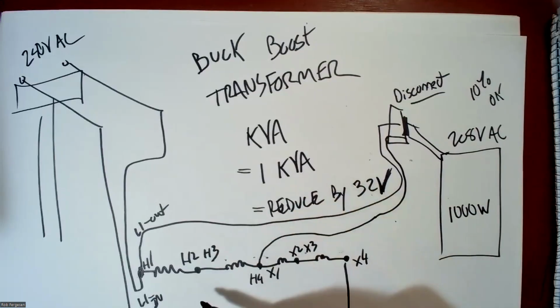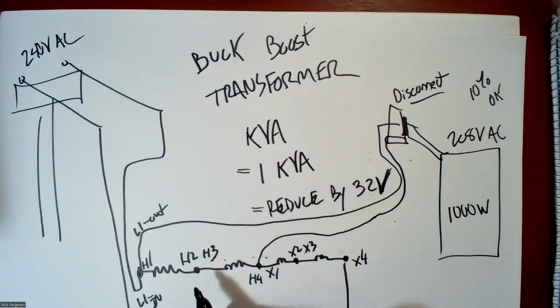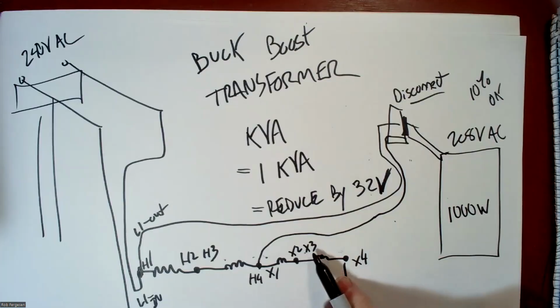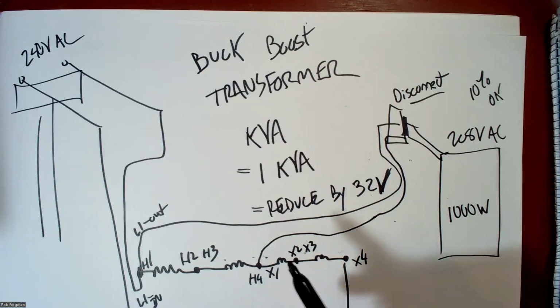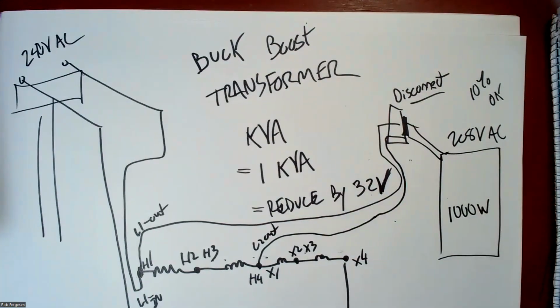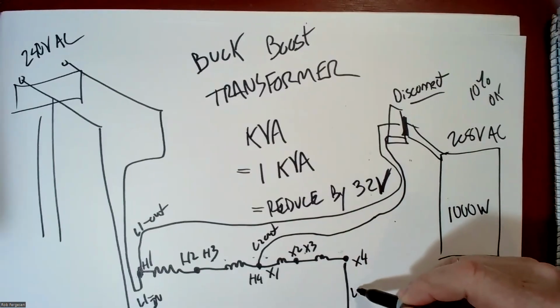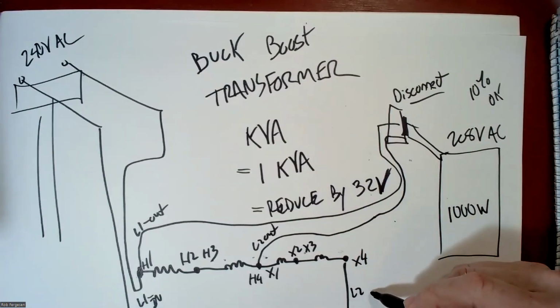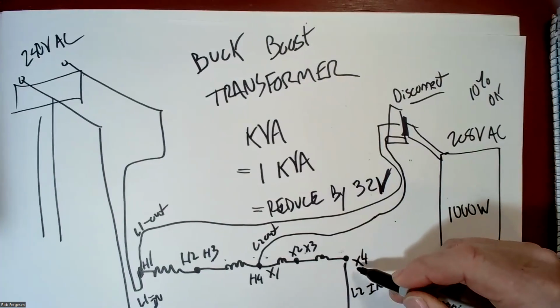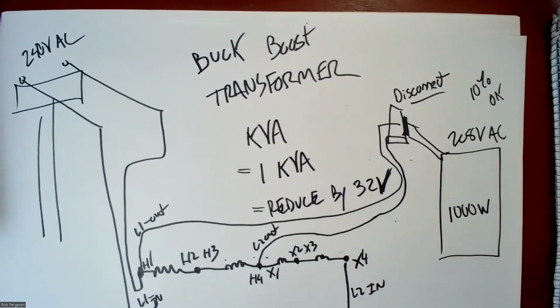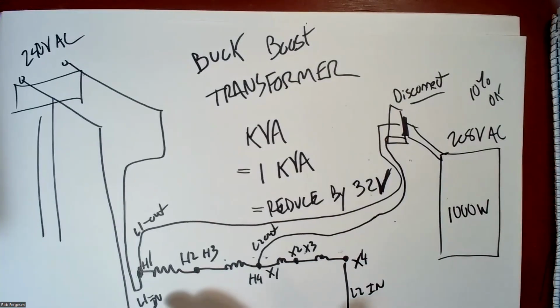When I say jumper, I mean you just wire nut them together. You're going to wire nut those leads together. You're going to wire nut these leads together. You're going to wire nut the output on L2 to H4 and X1, and you're going to wire the input on L2 to X4. So you're just going to wire nut those 2 together. That way you've got your power equivalent going in and out, but you're doing a voltage reduction on the output side.